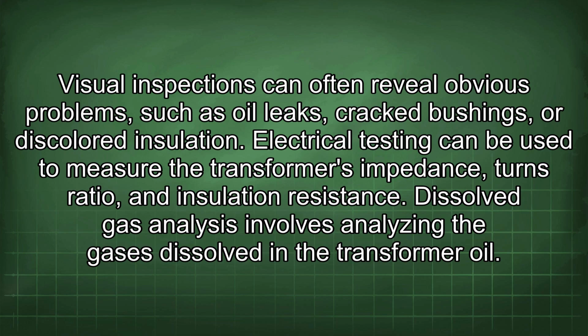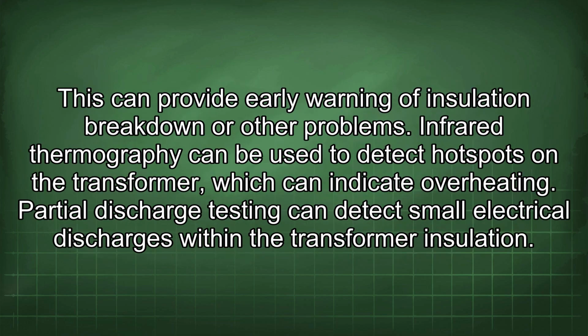Dissolved gas analysis involves analyzing the gases dissolved in the transformer oil. This can provide early warning of insulation breakdown or other problems. Infrared thermography can be used to detect hotspots on the transformer, which can indicate overheating.